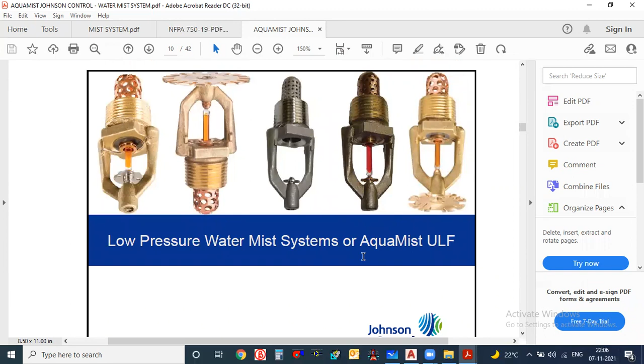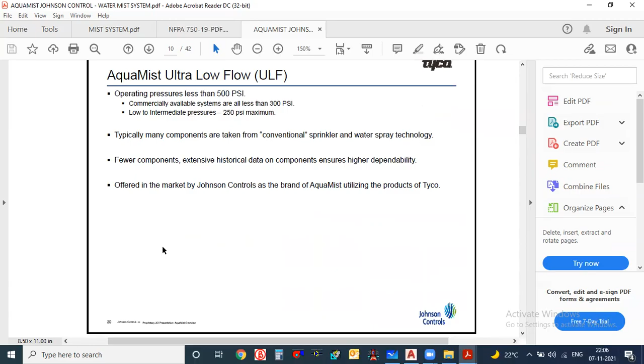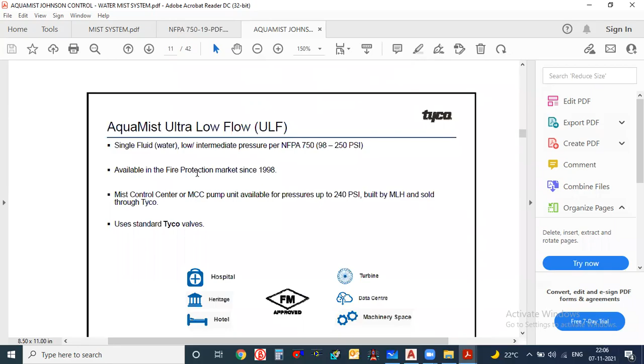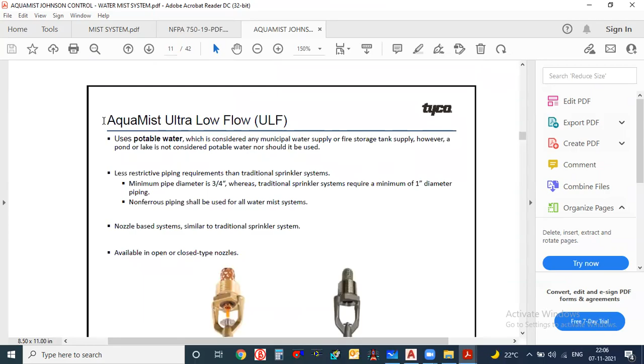Then they discuss the low pressure water mist sprinkler system, specifically the Aqua Mist ULF, with operating pressure less than 500 psi, or less than 300 for low to intermediate, commercially available, with many components taken from conventional water spray systems. They also give pressure ranges available, water usage details, technical orientations, K factor, and approvals for the sprinkler.